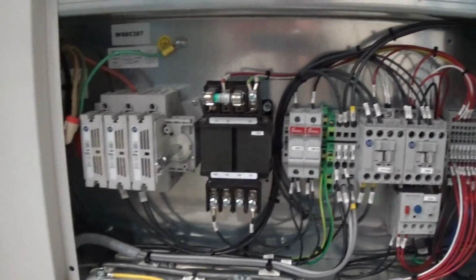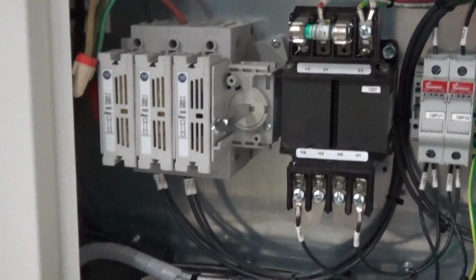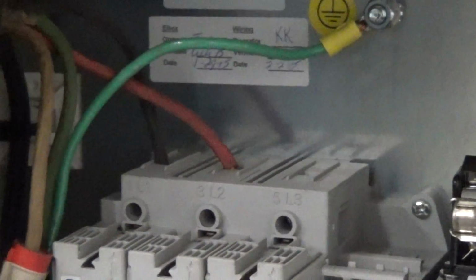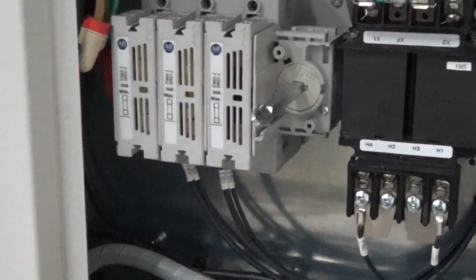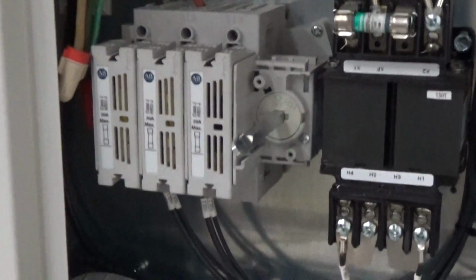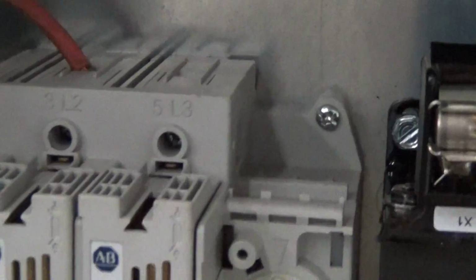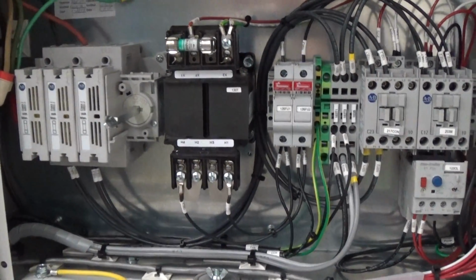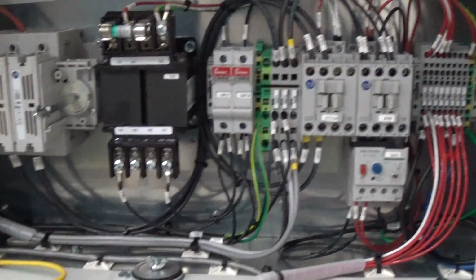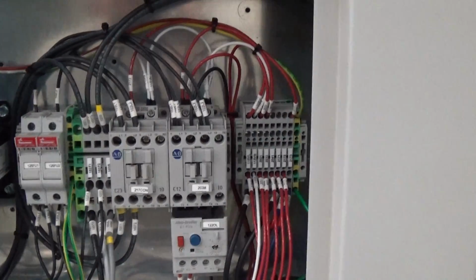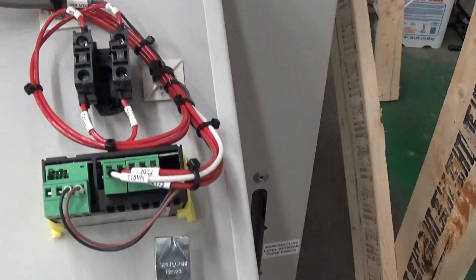Before I power it up, here's the inside of the controls. You can see it's obviously a brand new unit. You have your main disconnect there. It's single phase, so we don't have to worry about phase rotation. They just pulled a 3-phase disconnect off the shelf, so you have one line there, L3, that's not even being used. Then you've got your controls transformer, compressor fan contactor, pump contactor with overload, and this all goes to your Carel controls. I'm just going to put power to the unit there.